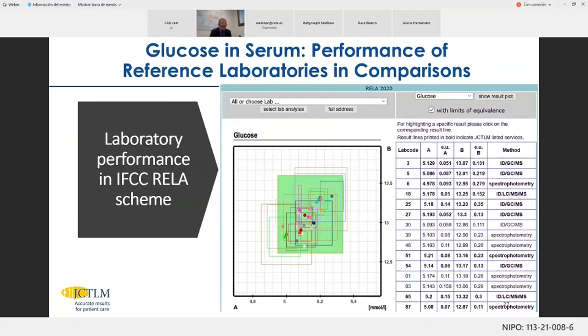And finally, that's not all. We also have secondary reference materials, secondary because of the calibration hierarchy, but these are matrix reference materials produced by national metrology institutes that have been value assigned by reference methods. Here for glucose in serum, we can see a particular material that's available, both to be used as a calibrator for industry, and if it is going to be used as a calibrator, it needs to also fulfill commutability requirements. Commutability is the property of a reference material where it acts as a human sample within the measurement system used by a manufacturer. That's an important issue. And those are available also for use or for validation of calibration hierarchies.